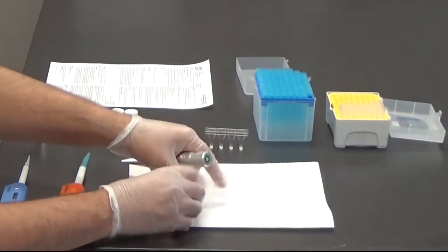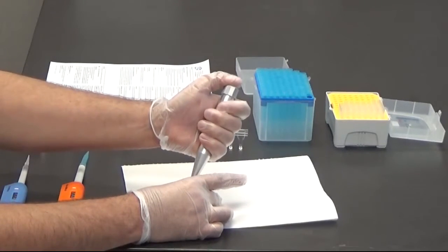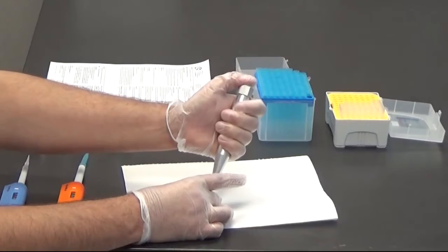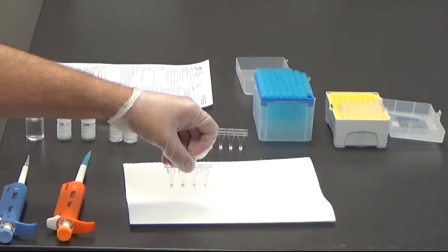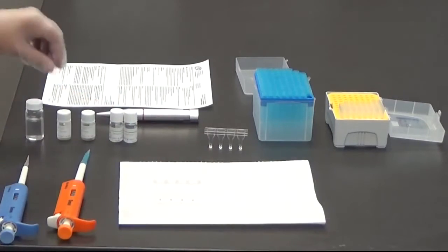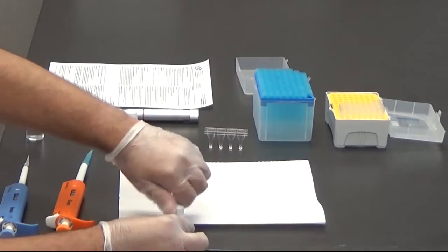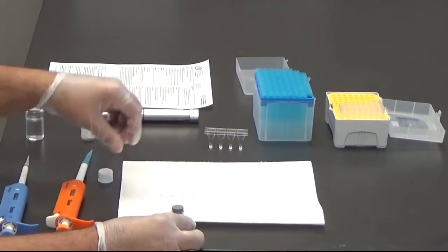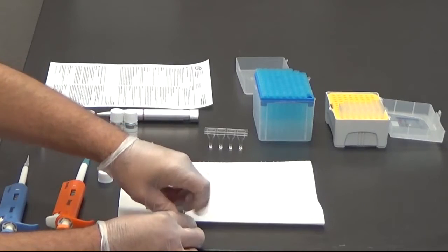The first thing the user will do is dispense steel balls into the cuvettes. To prepare the controls, they need to be reconstituted with 1,000 microliters of DI water. The controls are solid, and once the DI water is added, recap the vial and shake it to combine into a liquid.